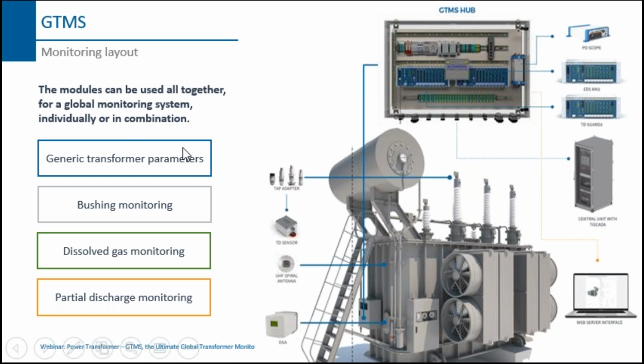On the right, the unit that we use to collect data from the sensor, and we have basically 4 different types of acquisition unit. The first one is PD scope for partial discharge. Here, EDS Mark III for generic transformer parameters, a unit dedicated to tan delta acquisition, and for sure the DGA. You can see here also a central unit where we can install our T-SCADA. It is a software platform that can collect all the information coming from the transformer and other assets installed in the substation.